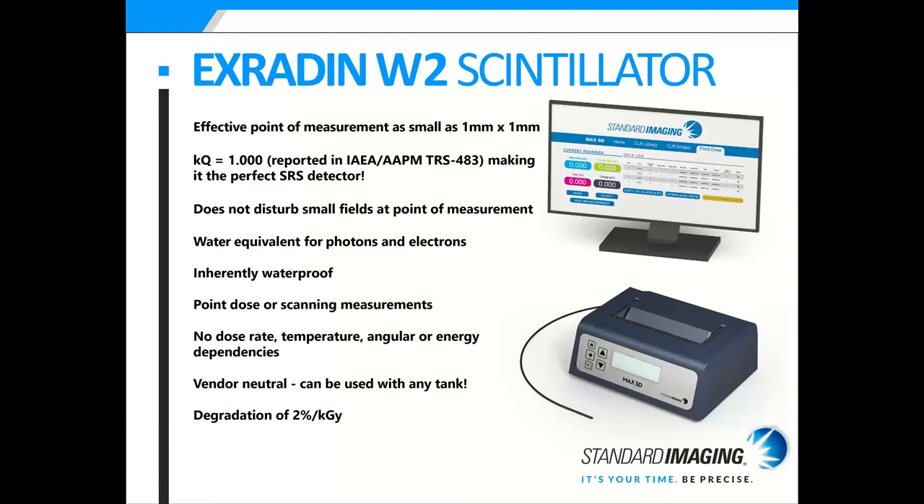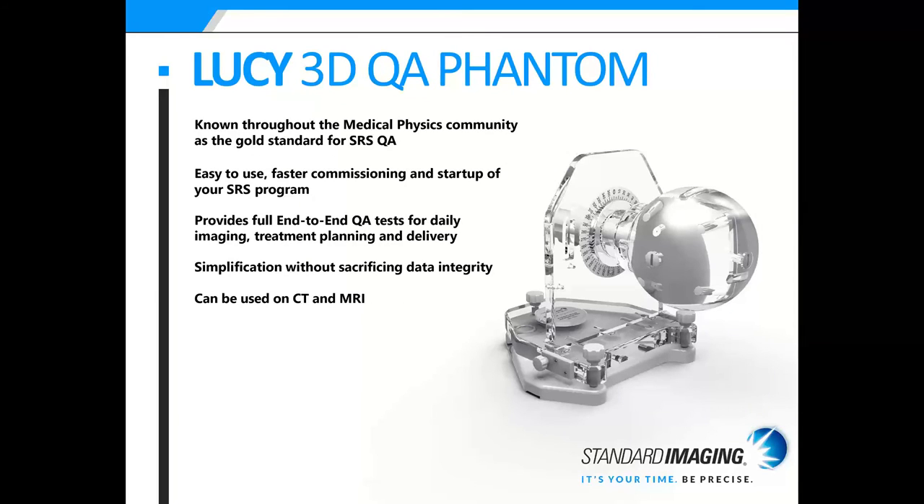For stereotactic products, we have the EXRADIN W2 scintillator, which has an effective point of measurement as small as 1 mm by 1 mm. It has a kQ of one, making it the perfect SRS detector — it does not disturb small fields at the point of measurement and is water equivalent for both photons and electrons. It is inherently waterproof, with no dose rate, temperature, angular, or energy dependencies, and is vendor neutral so it can be used with any tank. Degradation is 2% per kilogray, and once the fibers degrade they can be easily replaced. An MR-compatible version is coming very soon.